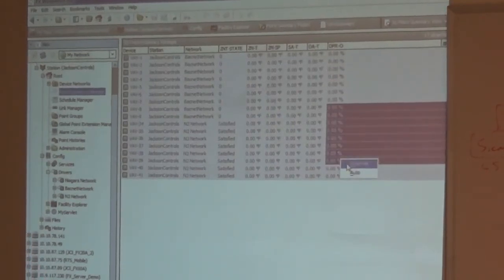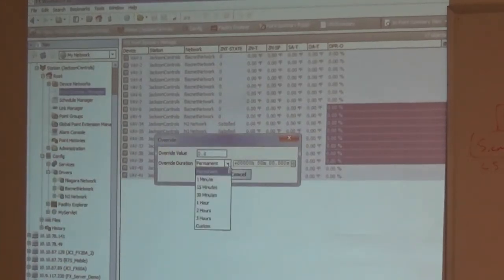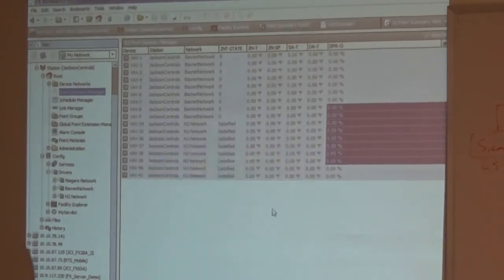So any point that's writable, you can do that. You can set up a view for a balancer, have them log on, override all the valve positions at 100%, or dampers at 100%, for whatever time override you choose there - 1 minute, 30 minutes, whatever, custom - and it'll do that.